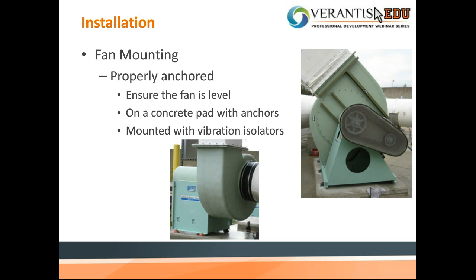So fan mounting, this is super, super, super important. You want to make sure the fan is properly anchored. The first step of doing this is ensuring that the fan is level. Ideally, you want this fan to be level on a concrete pad with anchors. We don't want these fans mounted on all thread that are supported in the air. We definitely want this on a base. We have seen occurrences where a fan has been mounted on all thread and is not on a secure level, and what happens, the fan starts vibrating and has the potential to damage the actual base itself, and then the issues get compounded and become a greater issue, and ultimately you may have to repair or replace the fan.